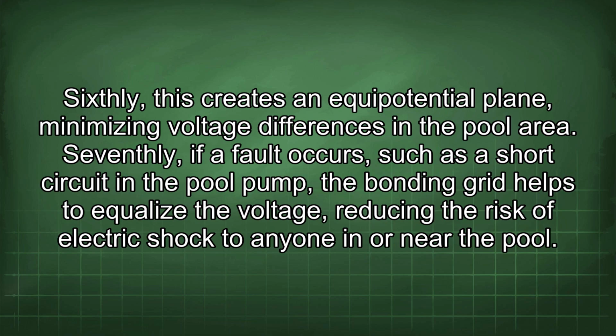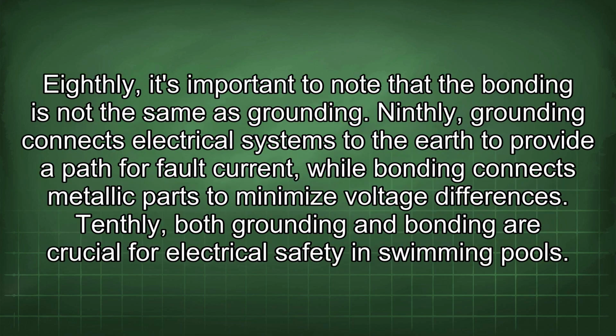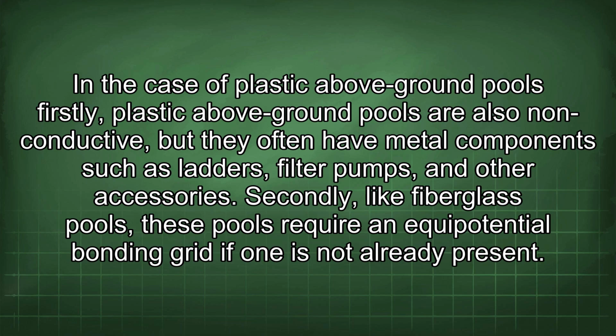Seventhly, if a fault occurs, such as a short circuit in the pool pump, the bonding grid helps to equalize the voltage, reducing the risk of electric shock to anyone in or near the pool. Eighthly, it's important to note that bonding is not the same as grounding. Ninthly, grounding connects electrical systems to the earth to provide a path for fault current, while bonding connects metallic parts to minimize voltage differences. Tenthly, both grounding and bonding are crucial for electrical safety in swimming pools. In the case of plastic above ground pools, firstly, plastic above ground pools are also non-conductive, but they often have metal components such as ladders, filter pumps, and other accessories.